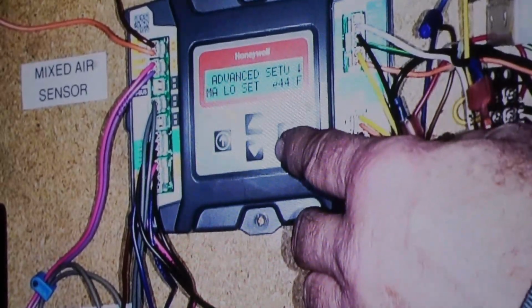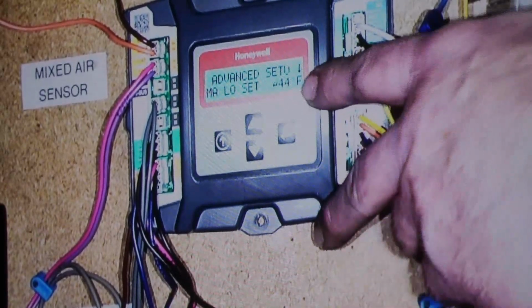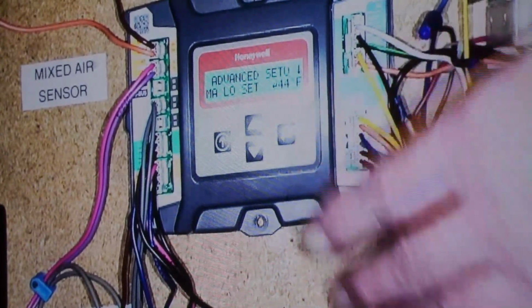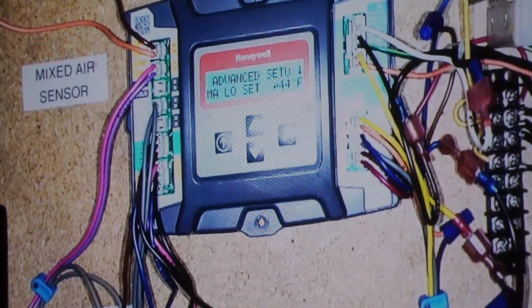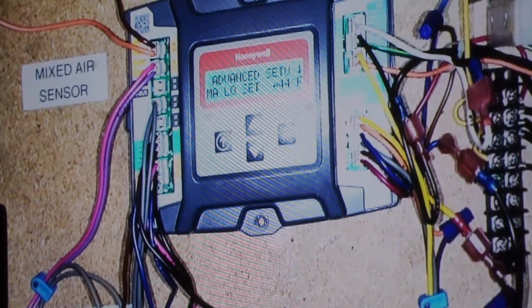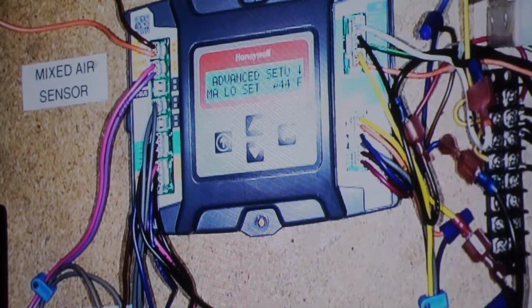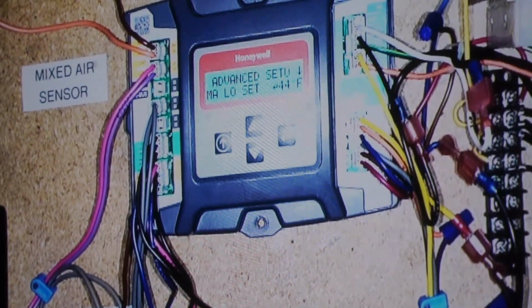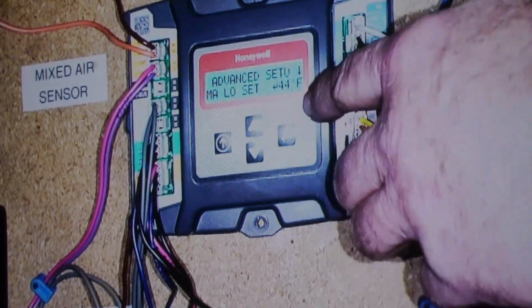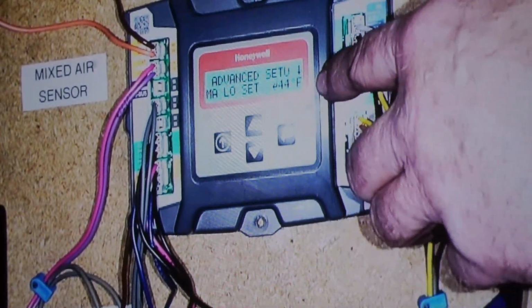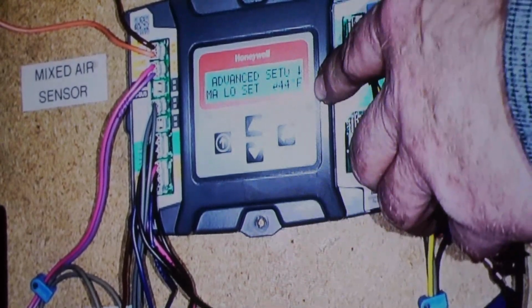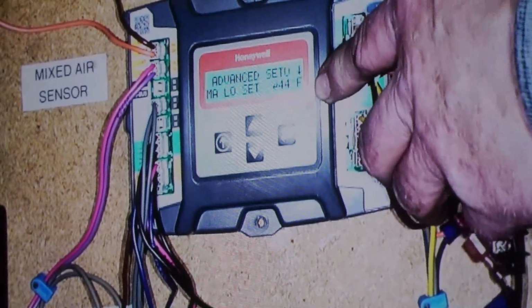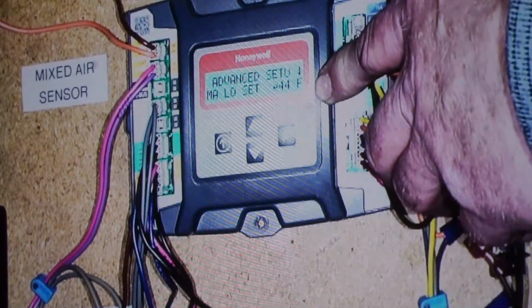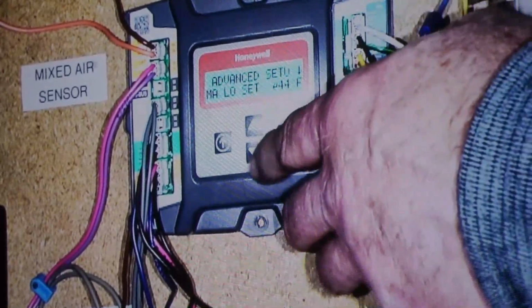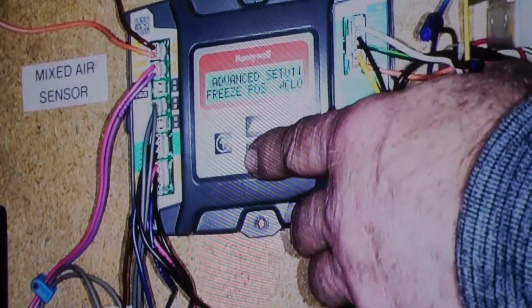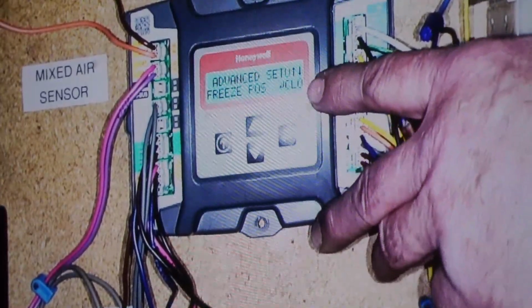Advanced setup is going to give us our mixed air low limit, 44 degrees. That's the temperature our mixed air gets to at which we close the outside air damper. So this is more of a freeze stat. It's not going to shut the unit down, but it's going to shut down all the outside air. So whatever temperature, 44 is pretty safe. I can go a little less if I wanted to, but usually if we're seeing 44 degree discharge air, we're either really low on air flow and our DX is overcooling, or we've got a problem with our outside air damper. And the freeze protection position is closed.